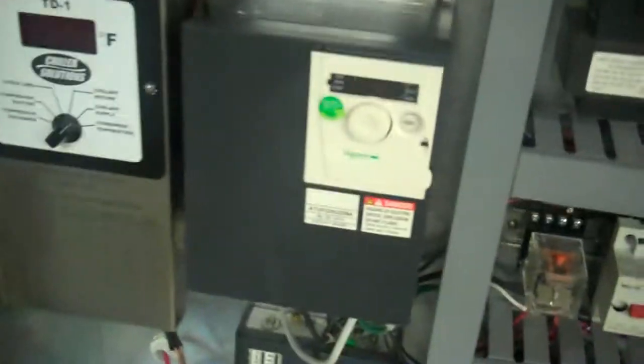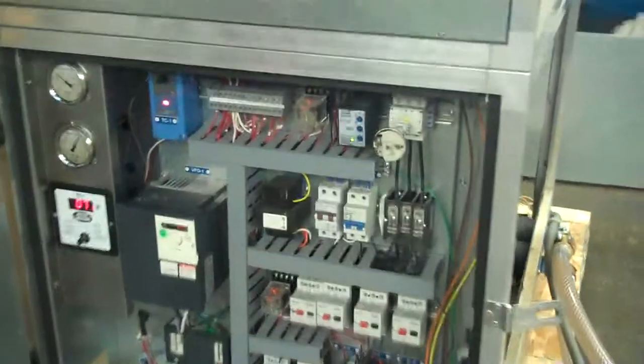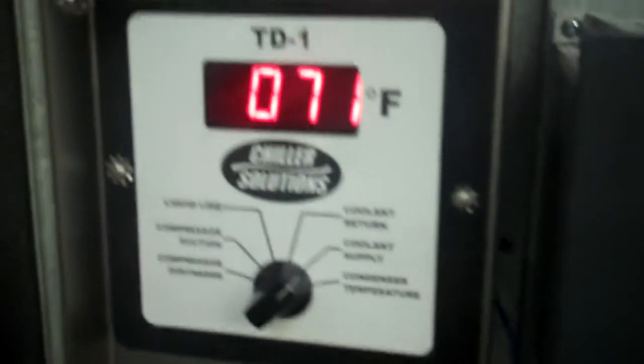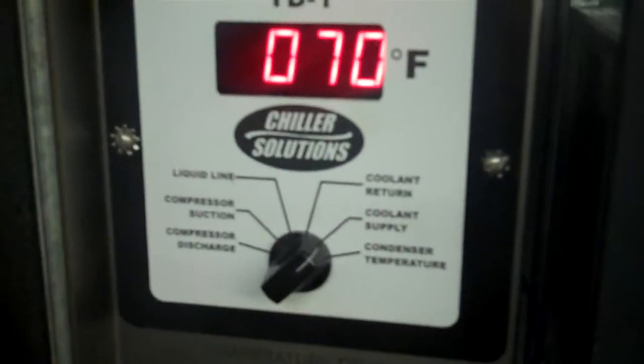We're going to do a runoff demo today. We've been testing and tweaking a lot of stuff here on the unit over the last few days, including the variable frequency drive right here. But we're going to go ahead and start the unit up right now. And it's already chilling right away. We have the temperature gauge here. The set point is achieved here. I'm going to cover this red light, it's so bright. By this Johnson Controls manual temperature gauge, we have it down to about 70 degrees Fahrenheit.